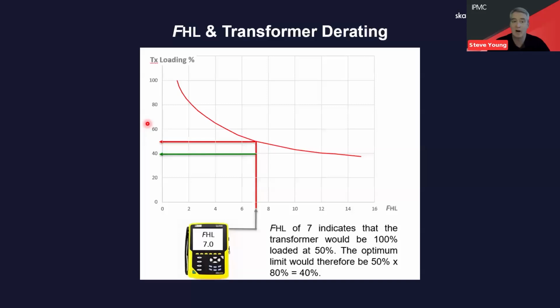So what about if we actually do have harmonics on the system, and most systems will nowadays? We're going to populate an example where we have a harmonic loss factor. Remember, this is measured by the instrument during typical peak demand, and in this instance it's an FHL value of 7. So we draw that line across and we take 80% of it. In our example of a 1000 kVA transformer, the safe limit of that transformer has been reduced from 1000 kVA, given the optimum limit and the consideration for harmonics, down to 40%, or 400 kVA. If we breach that line, then we're at significant risk of an exponential rise in distortion, unwanted heating, and problems.